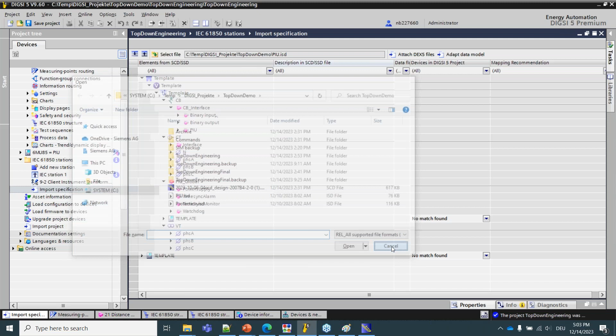The merging unit that is expected to be delivered at the end of the engineering process contains those logical devices, the CB interface, the CT interface, the VT interface, and so on. We'll do the engineering starting from the substation section. For that, let's go to the circuit breaker structure, where we find the most important functionality of the merging unit, being the position of the circuit breaker.